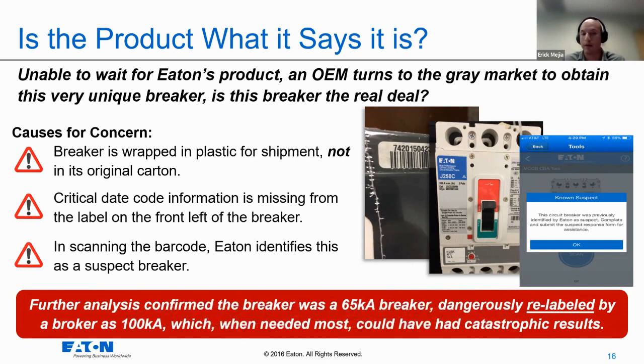For example, this breaker right here was confirmed to be a 65K breaker, but it was relabeled as 100K. So there are a couple things to keep aware of — if the rating on the breaker doesn't match what the packaging says, that's a huge red flag as well.